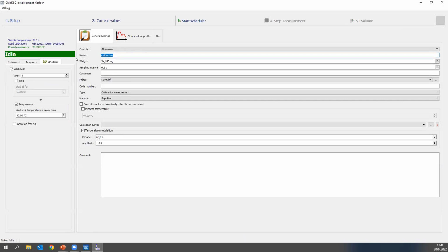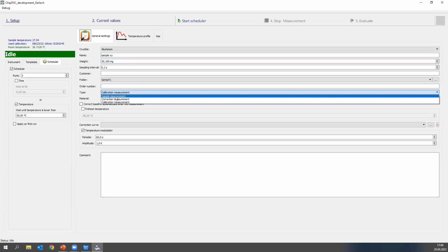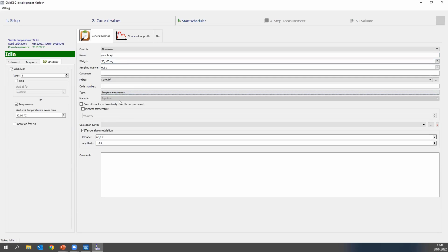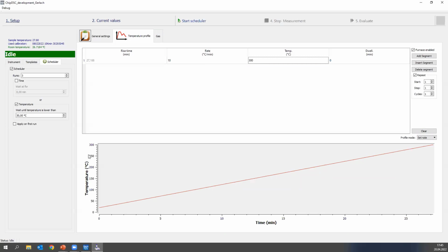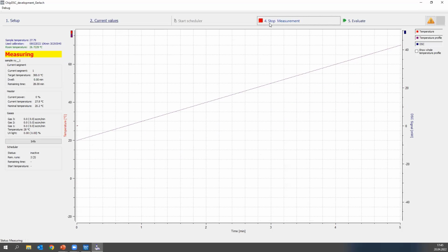And last but not least, we want to measure our sample. Also here, of course, we have to adjust the name and the weight. For example, it's 20.1 milligram. Now we can choose the sample measurement. There's no literature value, because mostly we don't know what we want to measure. And that's it. We don't change the temperature modulation, we don't change the temperature profile, and we also don't change the gas profile if there is any. Then we can start the scheduler again, and that's it.